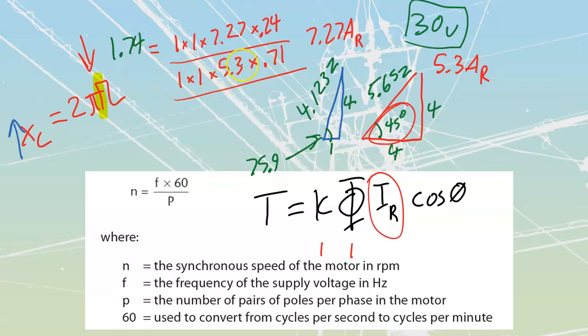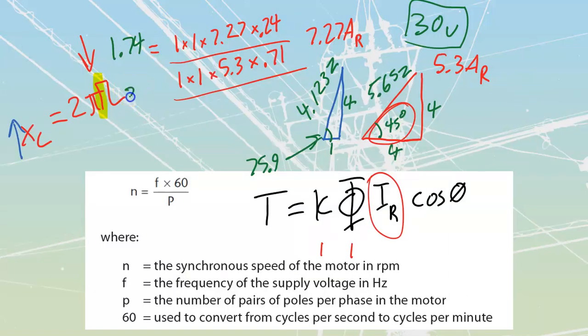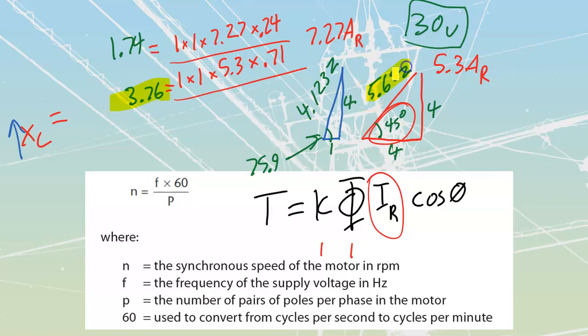Holy crap - we have a complete winner in the torque battle! Even though they have relatively similar values of impedance, it is the fact that the 45° triangle gives a really good angle compared to the poor 75.9° angle, allowing us to develop almost double to nearly triple the torque. This really good triangle is defined anytime resistance R is approximately equal to reactance XL.